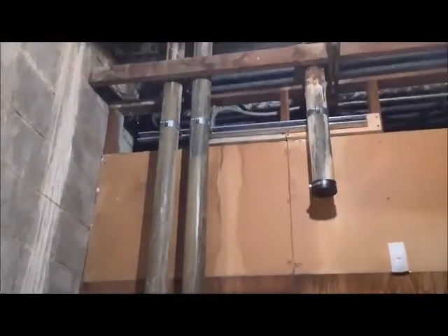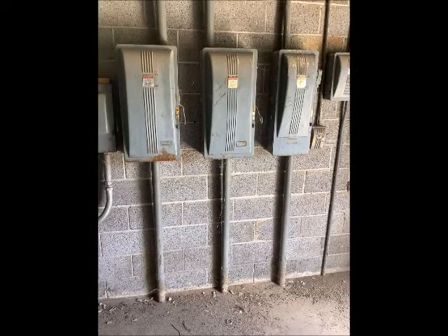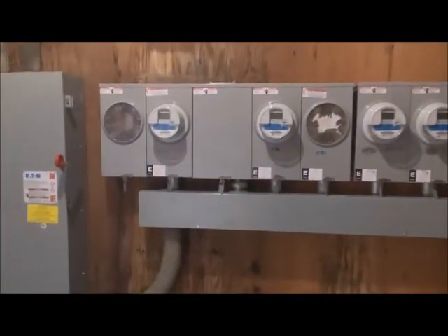Done deal. That was a riser that was feeding it three-phase. The panel that was here, and on this wall over here, all of them disconnects that was over there — remember them? Old disconnects, it's all cleaned out now. I just got those three-inch nipples sitting down there. We got the old light switch there. Inspector Lovett — they're all inspected by the City of Tulsa. Six inspection stickers, final inspections. Everything is done.